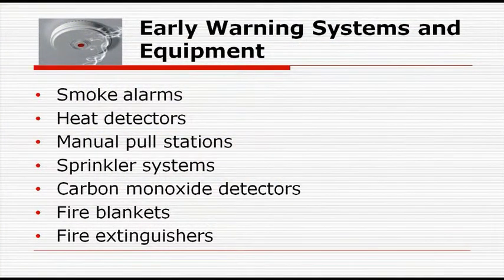Manual pull stations. Manual pull stations are those little red boxes that you can pull down. You see them in a lot of schools, and an alarm will go off. Now, what you need to know about manual pull stations is that if you set one of those off, you need to know whether you need to call the fire department or if they are automatically notified. It could be either way. So, whether you have to call the fire department or not, you need to get the fire department there to manually reset those for the next use.